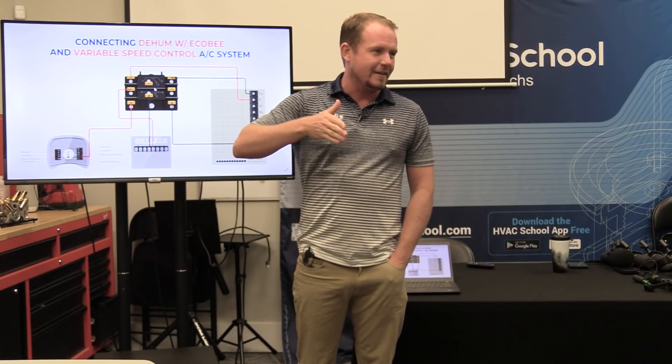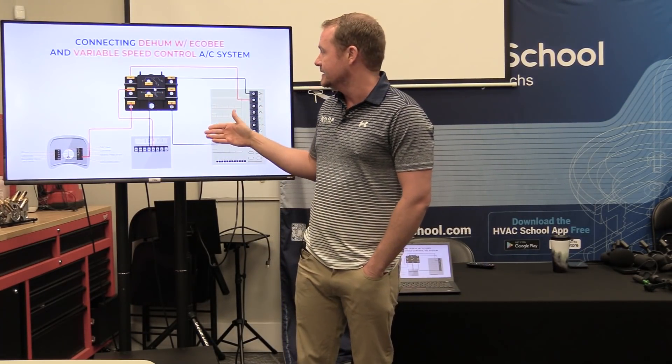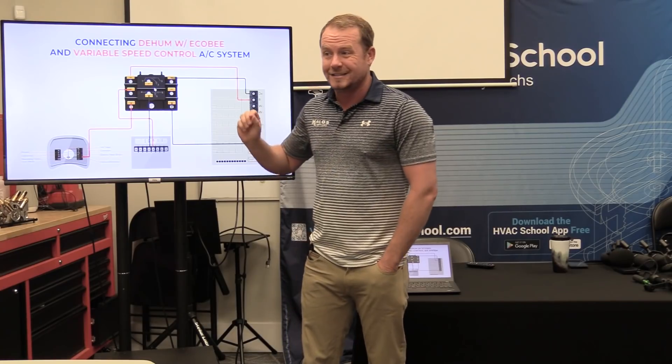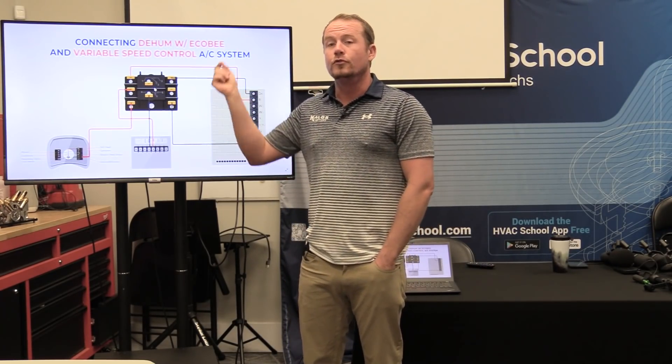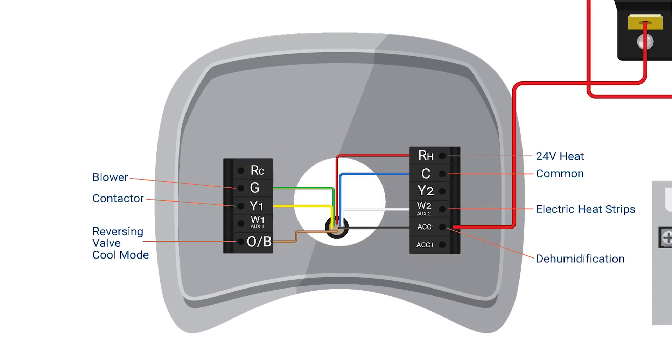And so this is an opposite way of thinking than what we would normally think. Because normally, when we want something to be in its normal state, it's de-energized. And then we energize it to change its state. In this case, the normal state requires DH to be energized. And when we drop DH, when we remove power from DH, that's when it goes into dehumidify mode.